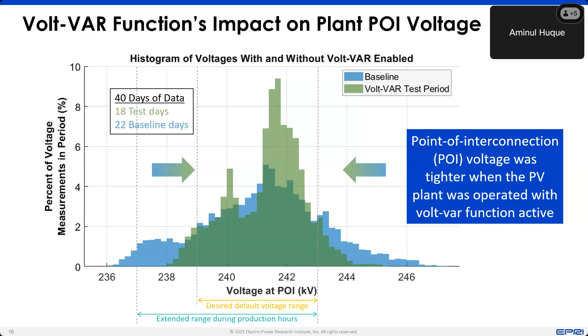And you can clearly see that on the days when the Volt-VAR function was active, the voltage spectrum was tighter and more centered around the target value of roughly 240 kilovolts, compared to the baseline days, the blue curve, where there was no reactive power or voltage control support from the plant. So overall, over 18 days, it maintained the voltage much tighter compared to without any control or support from the plant.